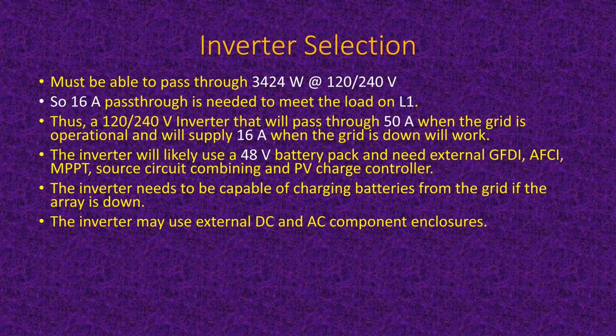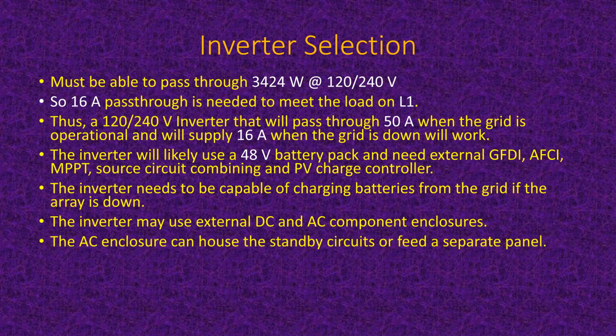It might use some external DC and AC component enclosures, like that spare backup load panel that we showed in a previous drawing. The AC enclosure might house some of the standby circuits. The DC enclosure might be where you combine all of the different things from the array and the batteries and the charge controllers and so forth, and have some separate circuit breakers for all those things so you can shut them down if necessary.